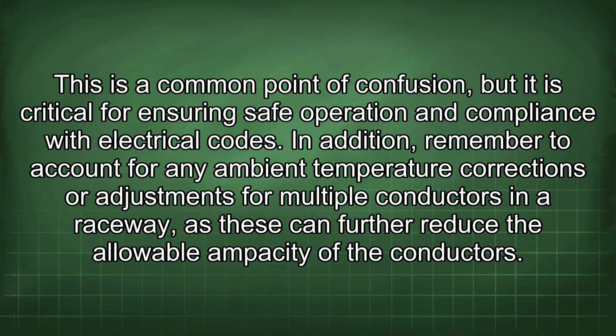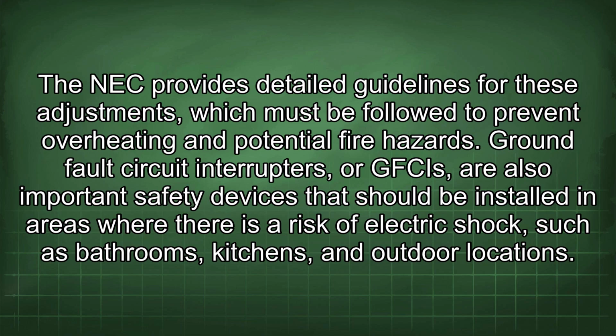In addition, remember to account for any ambient temperature corrections or adjustments for multiple conductors in a raceway, as these can further reduce the allowable ampacity of the conductors. The NEC provides detailed guidelines for these adjustments, which must be followed to prevent overheating and potential fire hazards.